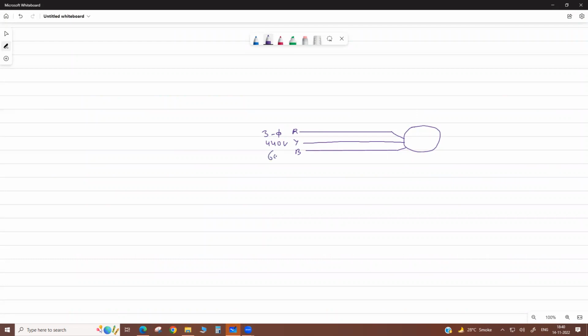So suppose it is a 440, 60 Hertz system, but the actual applied frequency is 50 Hertz. Then what is the impact on this motor? Actually, we know V by F is related to the flux density in the stator core. It is directly proportional to your V by F ratio. So if it is 60 Hertz it should be 440 by 60, correct? But actually it is 440 by 50. It means here flux density is increased.